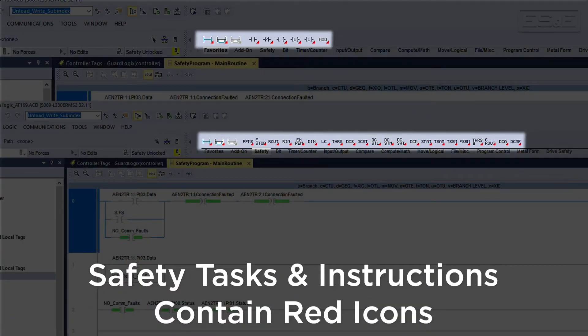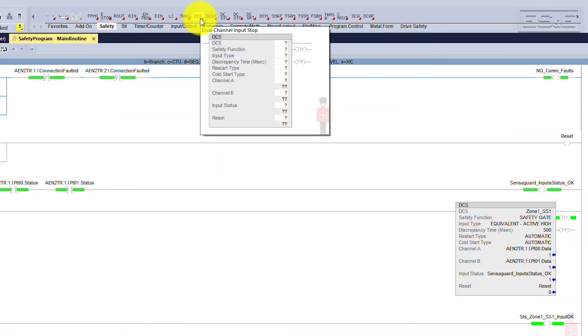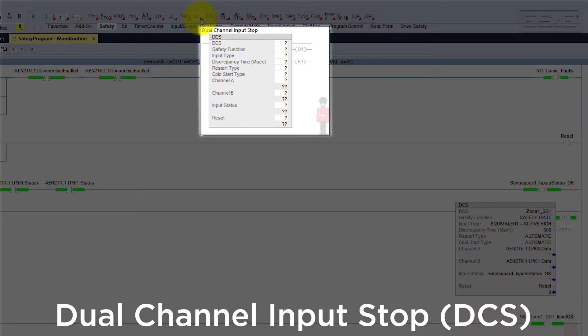The safety task and safety instructions stand out within Studio 5000 because they all contain a red icon to help differentiate them from the standard objects. When it comes to the safety instructions, you will only see them appear when you are within the safety task. Rockwell has preferred safety instructions, such as a DCS or dual channel stop, that monitors two safety inputs and is configured based on the safety function, input type, discrepancy time, and reset.